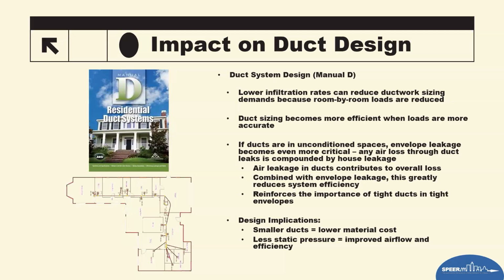It just doesn't waste energy. It also decreases the comfort as well. We've talked about that before. Not to mention poor performance of the system causing unrealized SEER efficiency and premature system failures. So if you have a system that is not running to its peak performance, that's going to interrupt it. Even though you look and say, oh, I've got an AHRI certificate that says I have a 15.2 system, but now you've got almost a ton of leakage in the attic, and you've got ducts that are compromised with how they're installed. That can now affect all the efficiency.